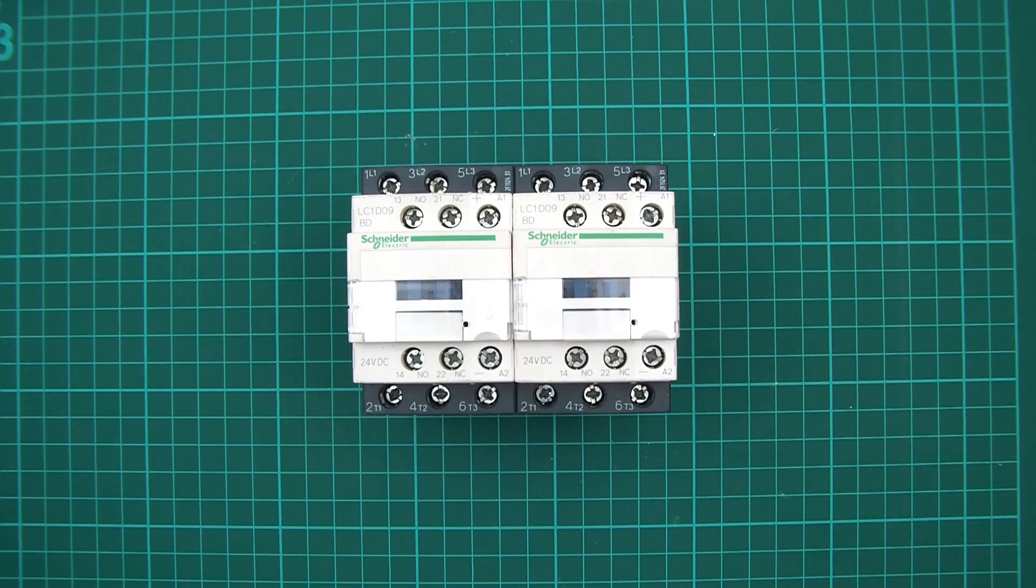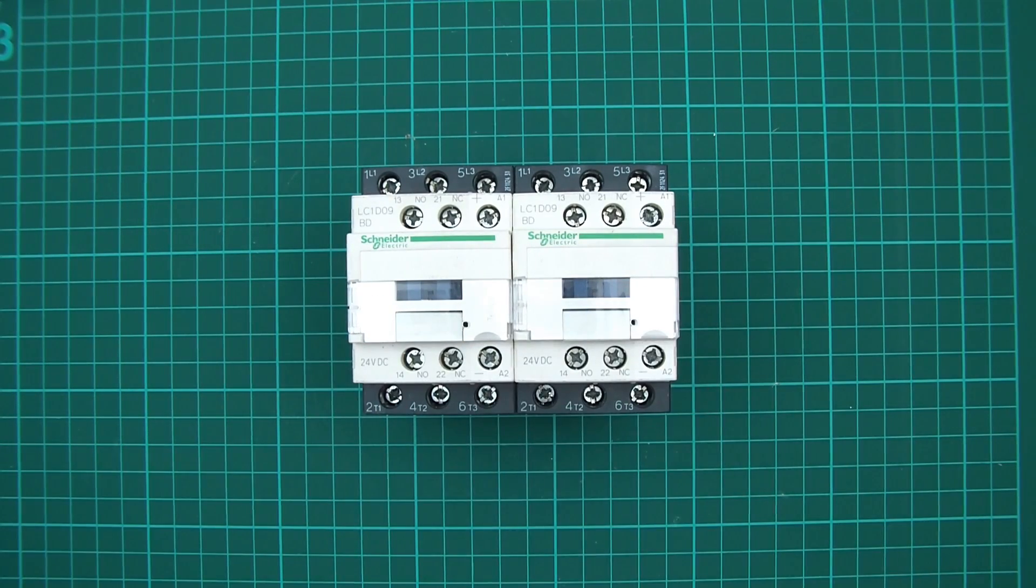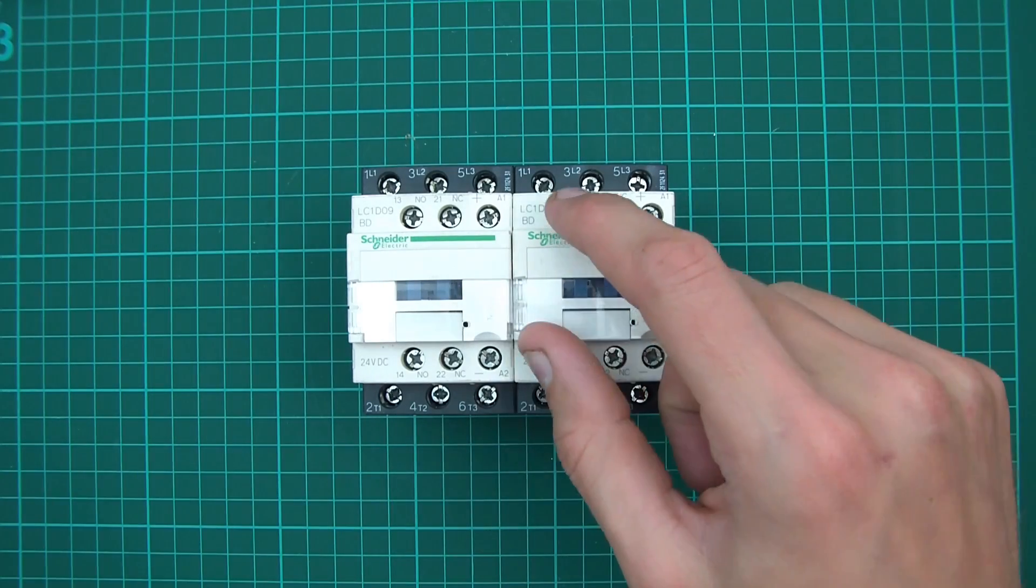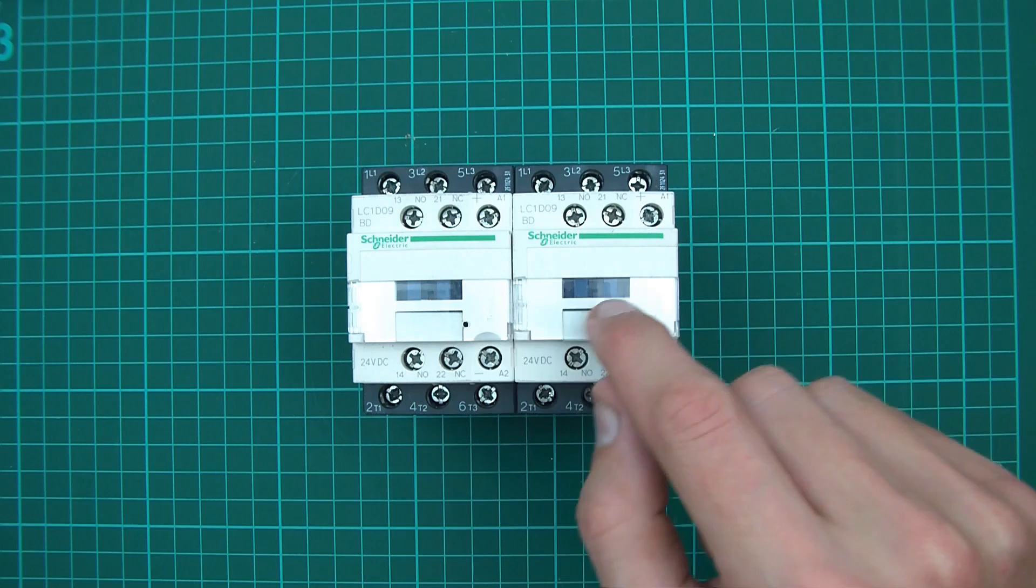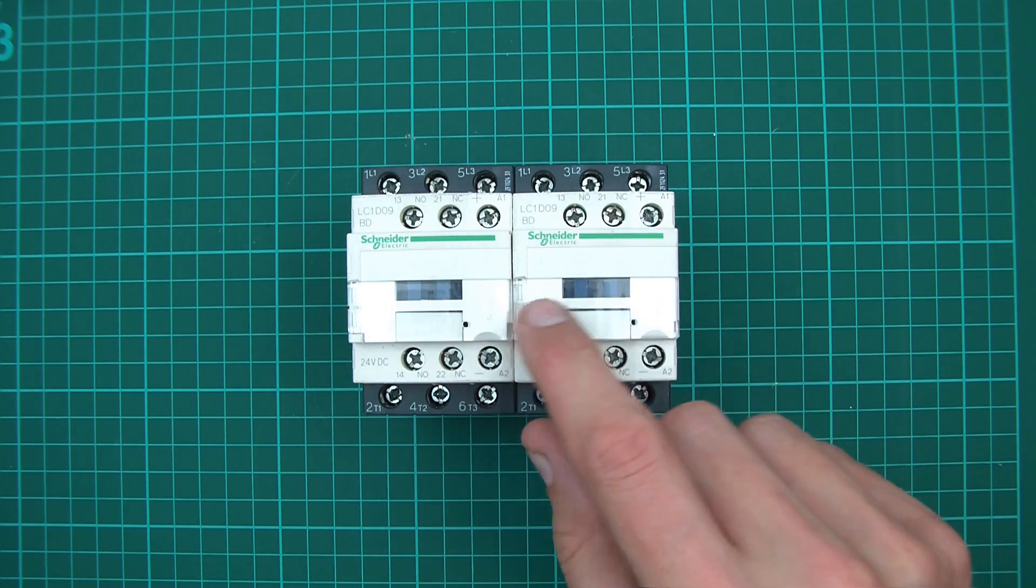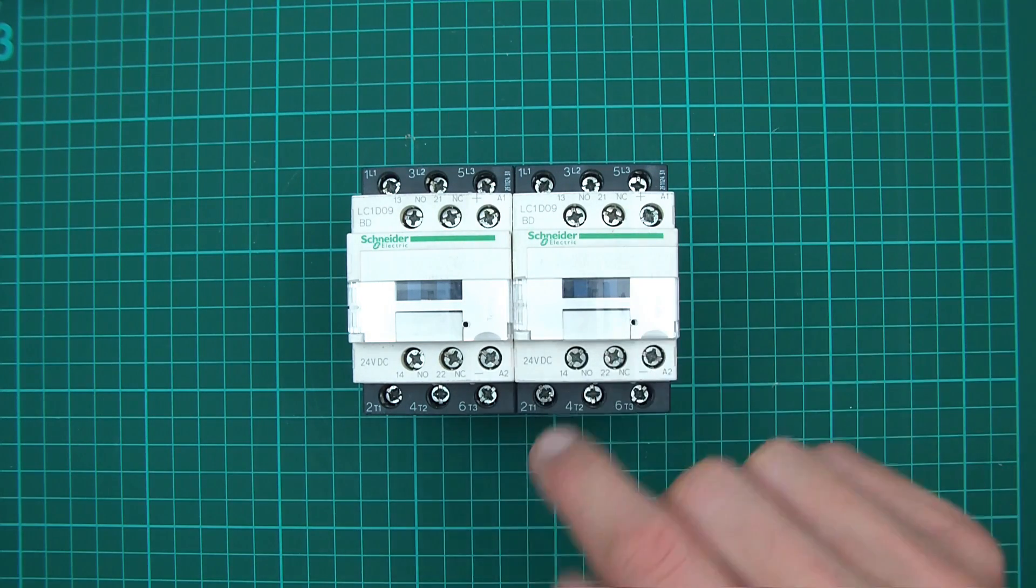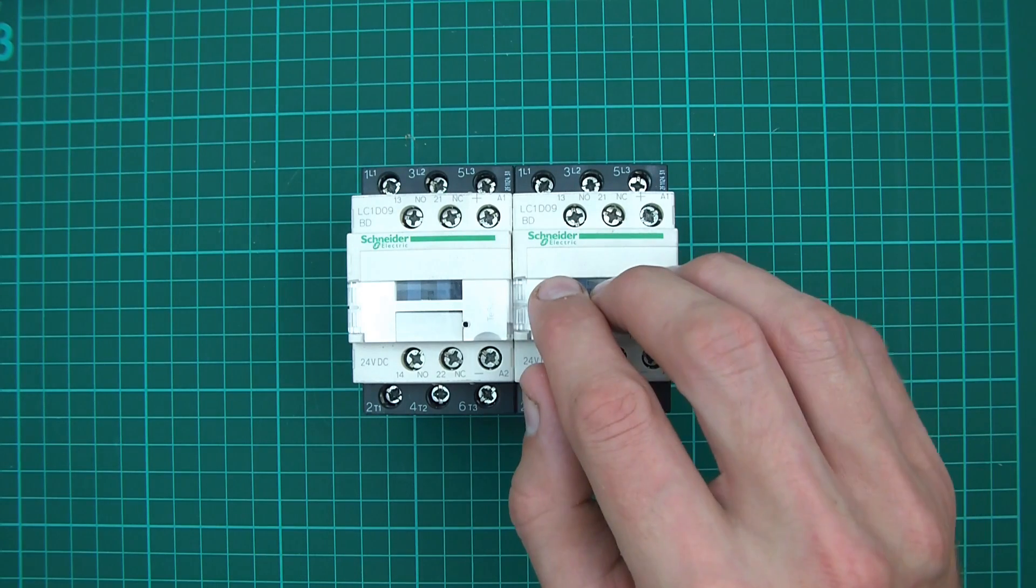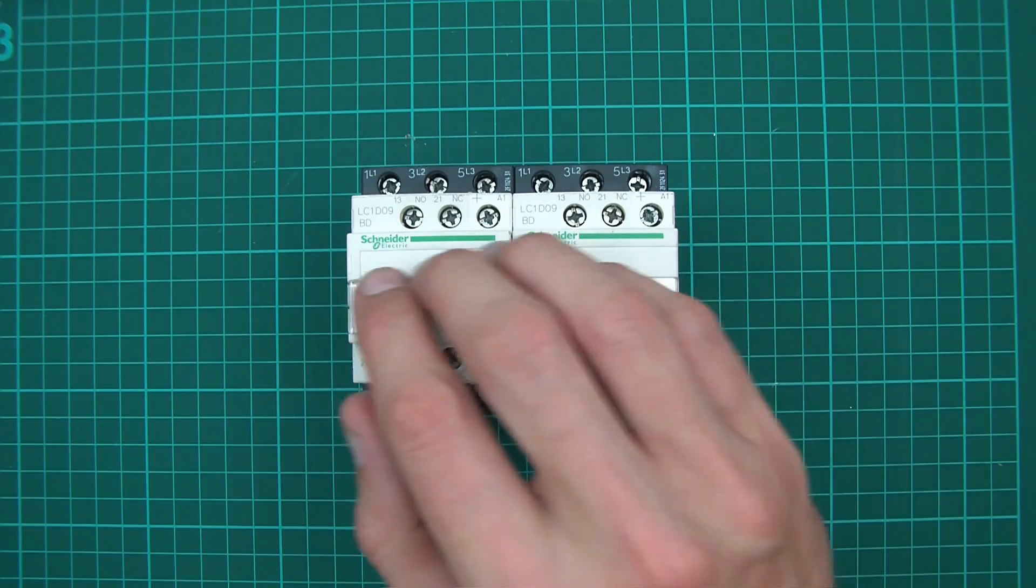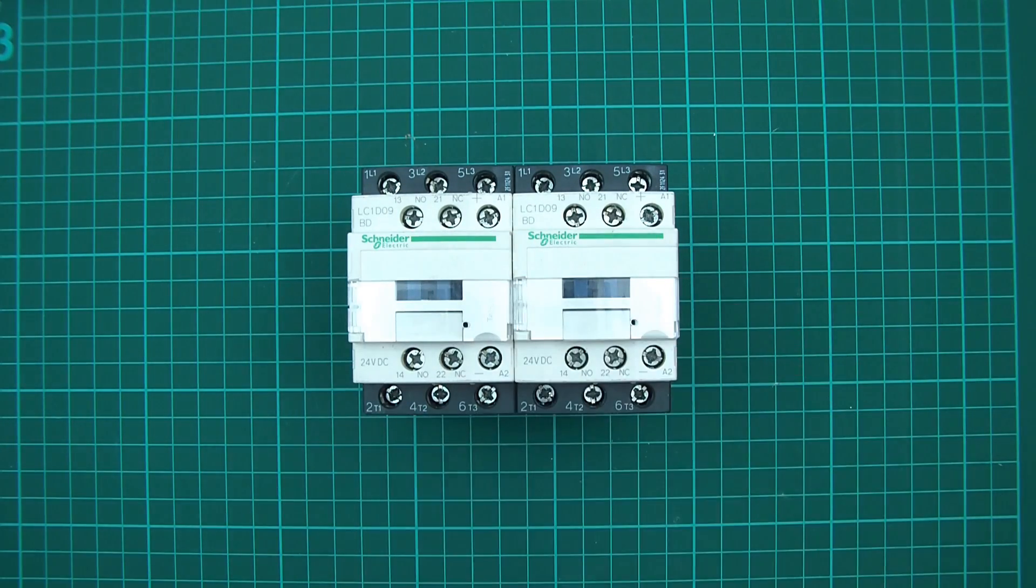There are other options. You don't actually have to use contactors, but I think they're probably the best. You can also use relays or you could switch the poles independently, but that's not really a good idea because inside the contactors there's a mechanical linkage so it switches them all at the same time.